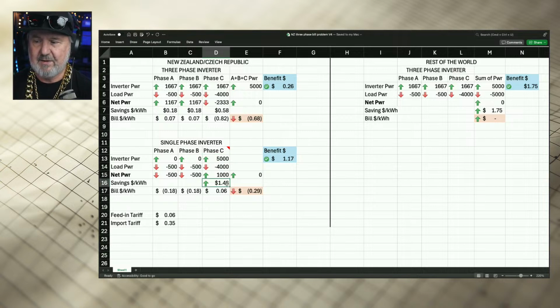So in this case the benefit goes up, because we're offsetting consumption on that heavily loaded phase, phase C. The overall benefit, including the electricity you had to buy on the other phases, is shown here, so you can see the difference. With a 3-phase inverter on 3-phase loads, the benefit's only about 26 cents because we're exporting 5 kilowatts. But when we put it all onto the heavily loaded phase, the benefit increases.